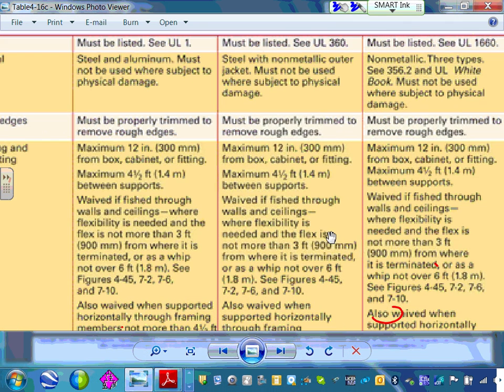Securing, I want to go to the securing right away. Securing and when you use, can I get you guys to highlight the following? 12, 12, and 12, and 4.5, 4.5, 4.5. Okay? So you support it every 12 inches from a box and 4.5 feet in between, with some fixture whip. Can you guys see? I'm going to highlight the fixture whip. Where is it here? Whip, 6 feet, 6 feet. Where's the whip here? Somewhere whip, and 6 feet. Is that whip? Whip. So can I use it as a fixture whip, gentlemen, to tie to equipment?